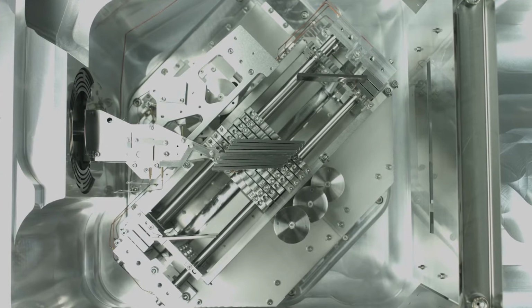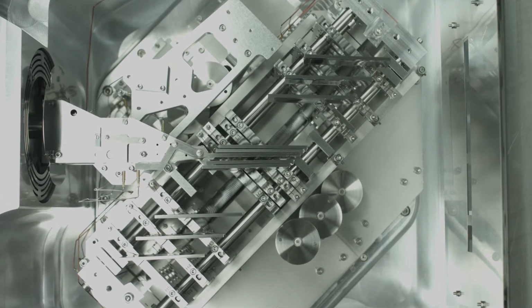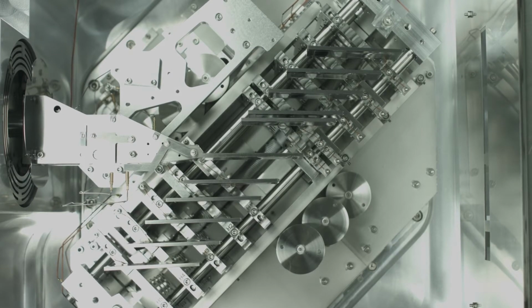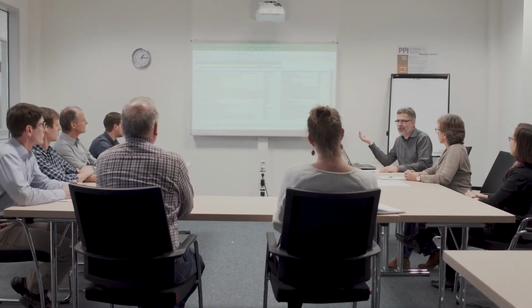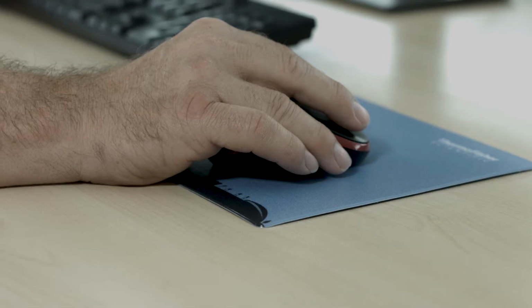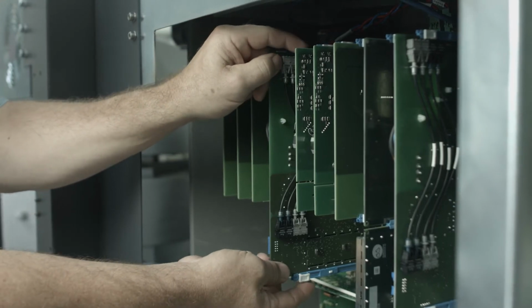Precise and reliable detector positioning aligns all 11 Faraday cups with ion beams of differing dispersions for analytical flexibility without limitations. Regular project meetings between R&D, engineering, and product management provided a forum for the valuable exchange of ideas and project status updates. State-of-the-art electronics were designed with specialized software, allowing for the 3D visualization of circuit boards, resulting in a compact design of high-voltage power supplies and electronic boards for improved stability.